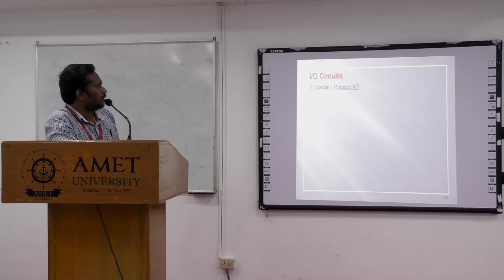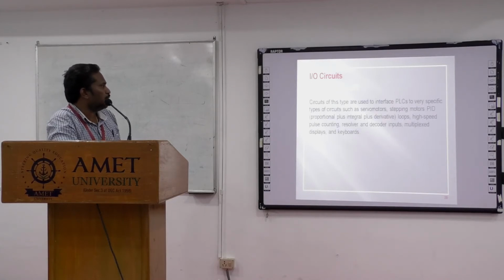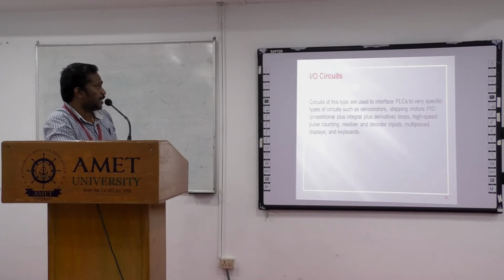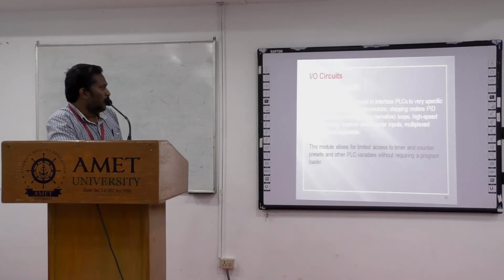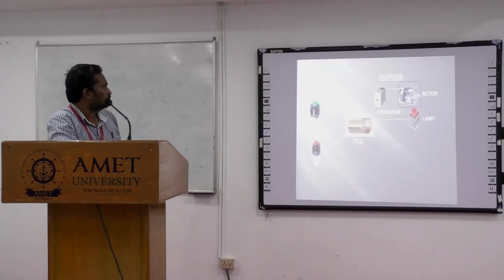The fifth one is special purpose I/O circuits. Circuits of this type are used to interface PLCs to very specific types of circuits such as servo motors, stepping motors and PID controllers. This module allows for limited access to timer and counter presets and other PLC variables without requiring a program loader. These are examples of input and output devices. Push buttons and switches are the inputs. Outputs are contactors, motor, lamp.